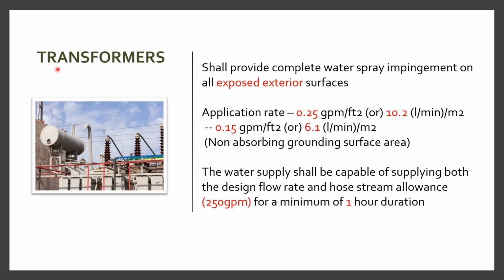So transformers shall also be protected with a water spray system. The water spray system shall provide complete impingement on all exposed exterior surfaces. The application rate for this would be 0.25 GPM per square feet. And below the transformer, there is a non-absorbing grounding surface area. That particular location shall also be provided with water spray nozzles. However, that location should have a design density of 0.15 GPM per square feet. The water supply shall be capable of supplying both the design flow rate and a hose stream allowance of 250 GPM for a minimum of 1 hour duration.